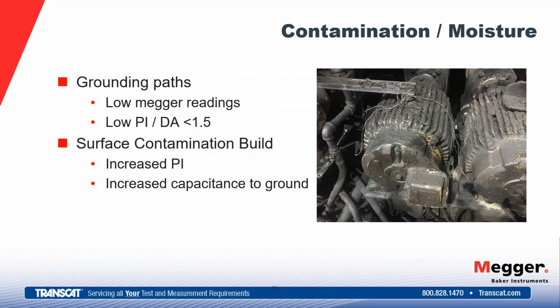Other things that low voltage insulation testing can help us with is to understand the contamination level or moisture level in the motor. So grounding paths, there are parallel paths to ground that contamination can give us, and it would cause lower Megger readings. It may cause a low PI or DA, something less than 1.5. So the contamination provides a parallel path to ground, and we're seeing that affect the low voltage insulation test. Could be surface contamination buildup, as we see on these motors here, a lot of grease and dirt built up on them, and the windings also. This increases capacitance to ground.